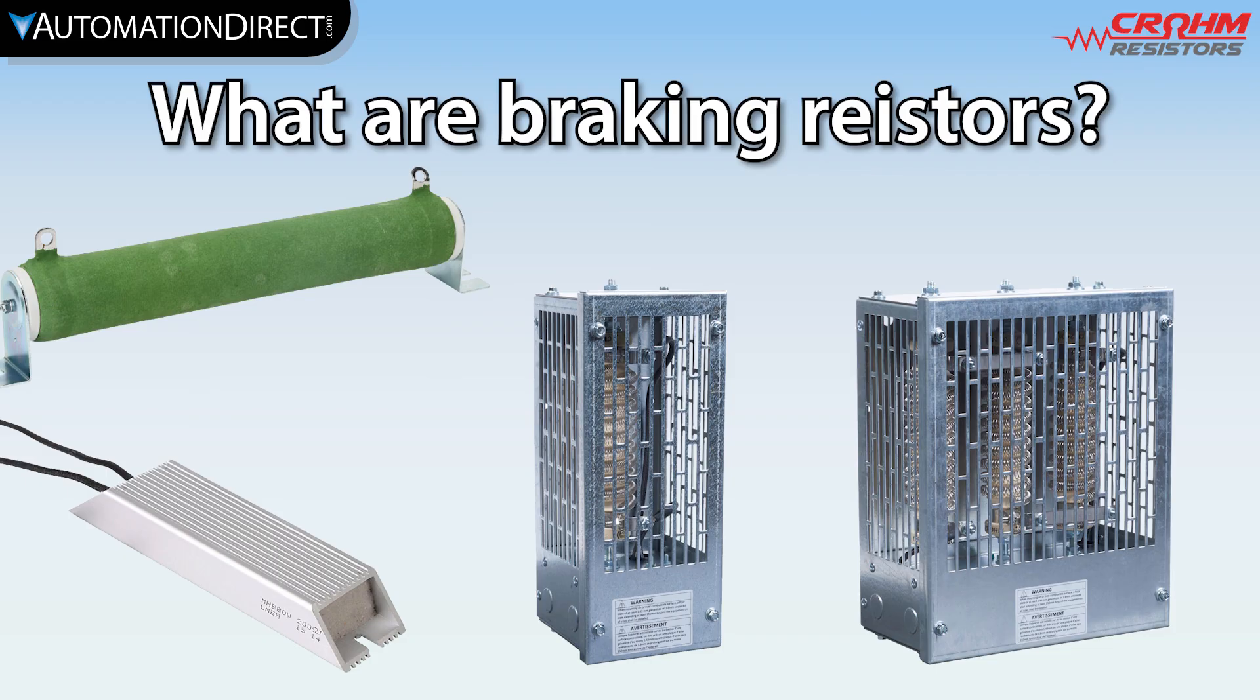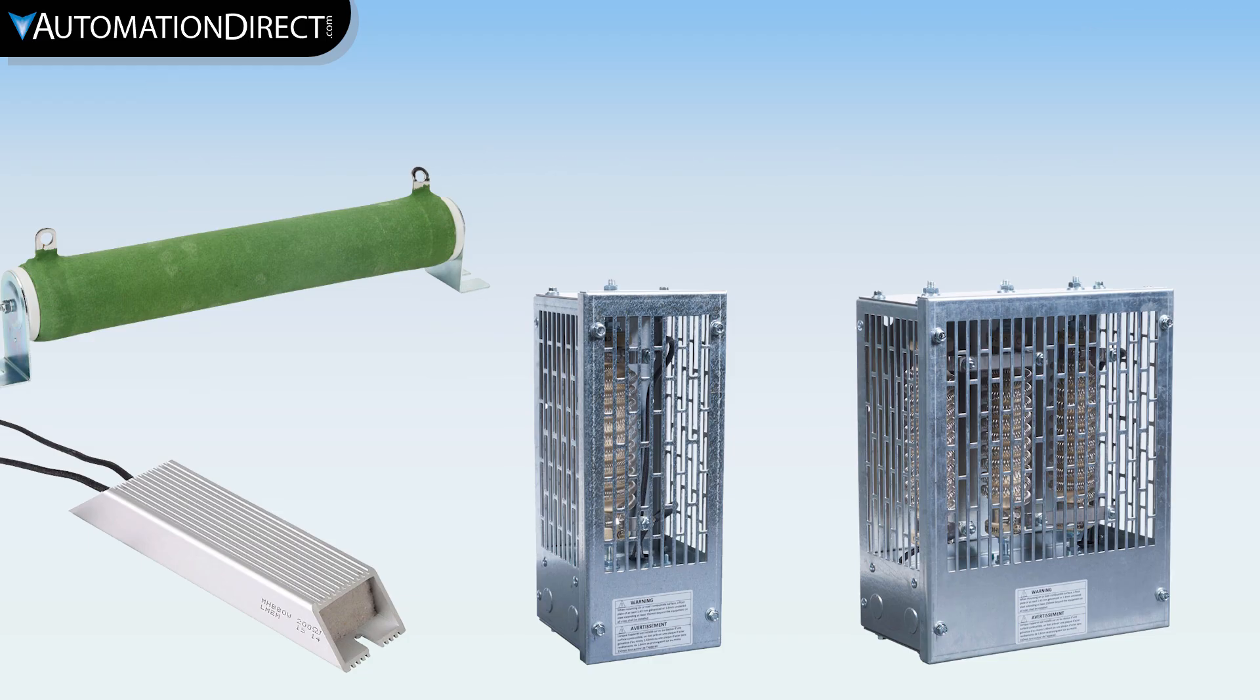Braking resistors don't actually provide braking directly. Rather, they allow a drive to stop a loaded motor faster. Yes, that may sound confusing, so let me explain.